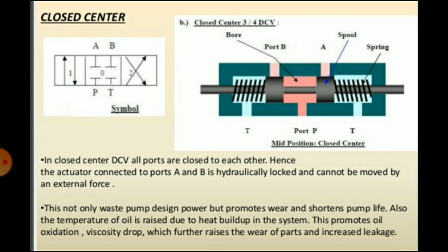and only when the valve is at center position it has different applications. So closed center: in a closed center position valve, all the ports are closed to each other in center position. The fluid finds its path to drain through the pressure relief valve, resulting in heat build-up in the system. Closed center position valve is used successfully in inching operations. It is desirable to inch heavy objects or while raising a load with a cylinder. It is advantageous to lift it in steps. This is achieved by the closed center position valve.